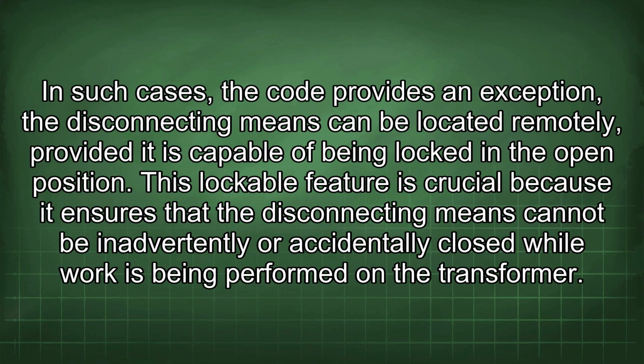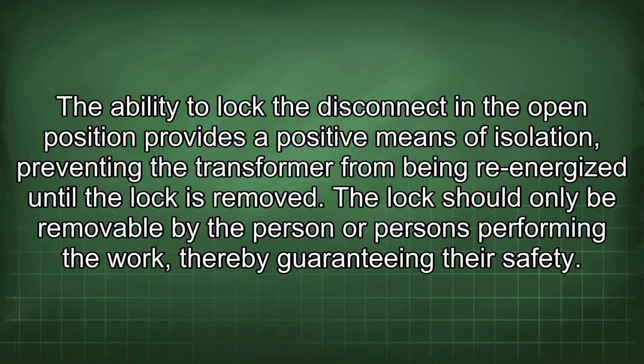In such cases, the code provides an exception. The disconnecting means can be located remotely, provided it is capable of being locked in the open position. This lockable feature is crucial because it ensures that the disconnecting means cannot be inadvertently or accidentally closed while work is being performed on the transformer. The ability to lock the disconnect in the open position provides a positive means of isolation, preventing the transformer from being re-energized until the lock is removed. The lock should only be removable by the person or persons performing the work, thereby guaranteeing their safety.